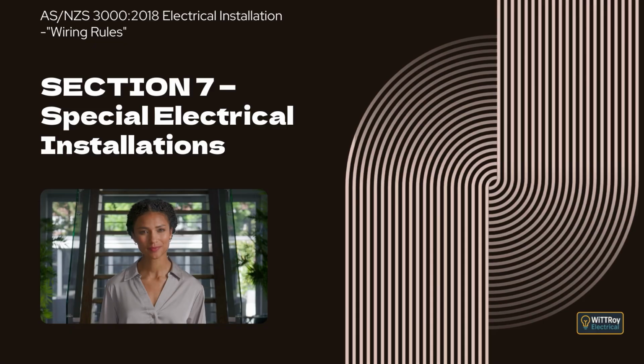Clause 7.3.6 Earthing. This clause explains that protective earthing in the electrical installation must use an MEN system in accordance with Section 5.